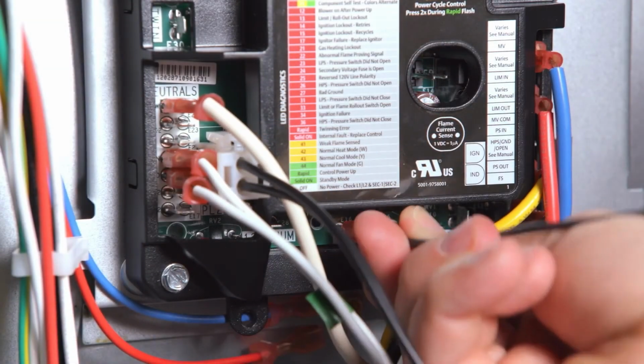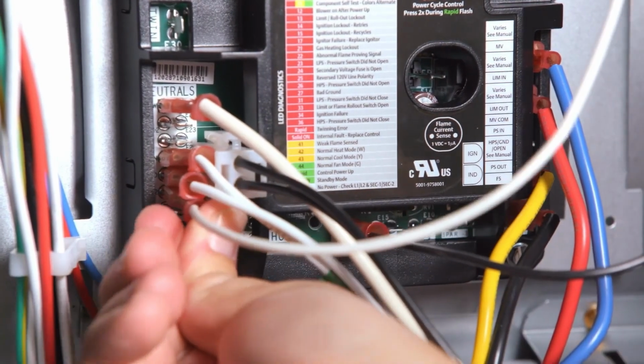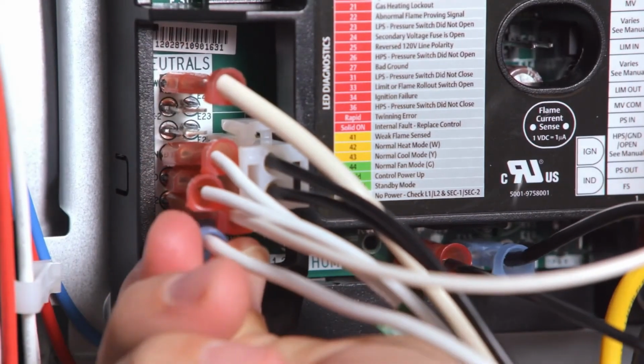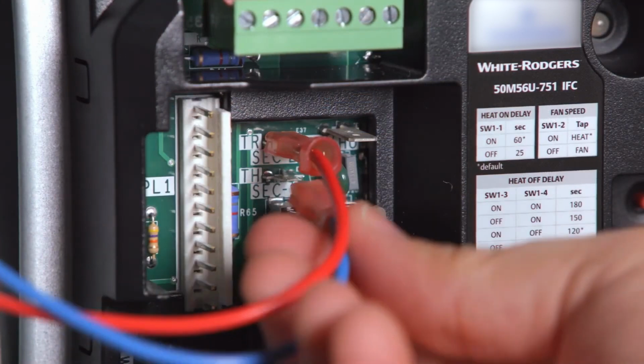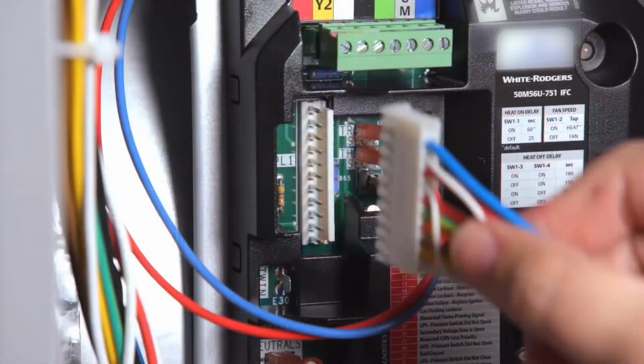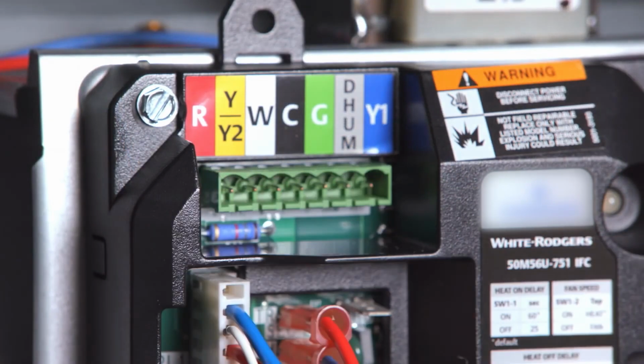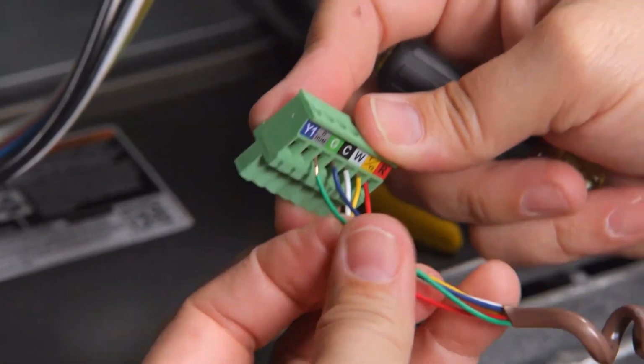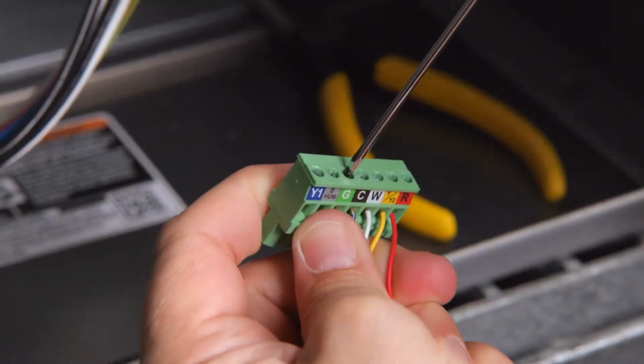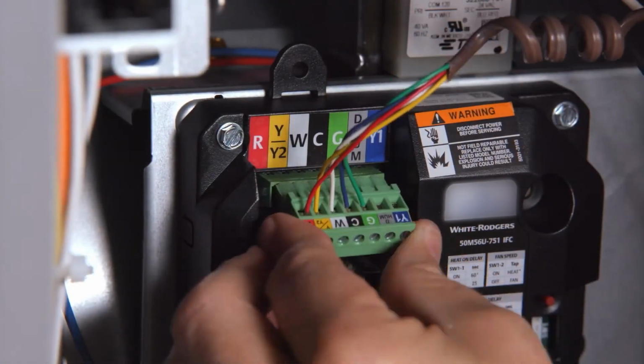Connect the 120-volt power and neutral transformer wires. Connect the 120-volt power and neutral wires. Connect the 24-volt transformer wires. Connect the Carrier inline plug. Remove the thermostat wiring block and install the thermostat wires required. Then plug back into the thermostat block.